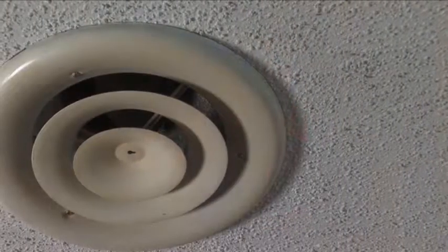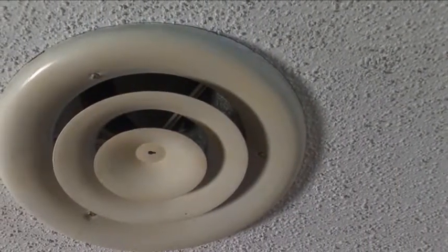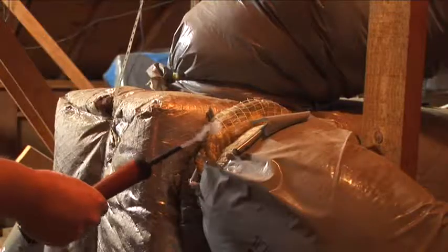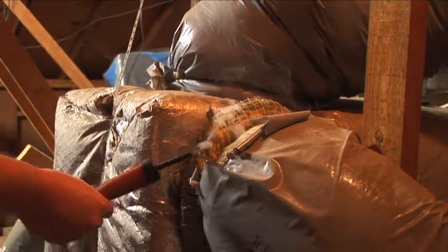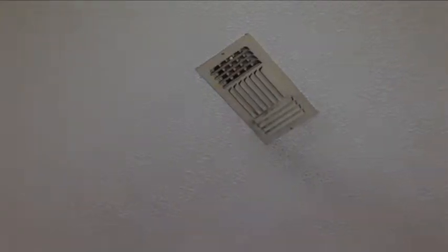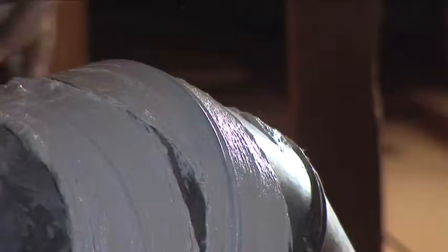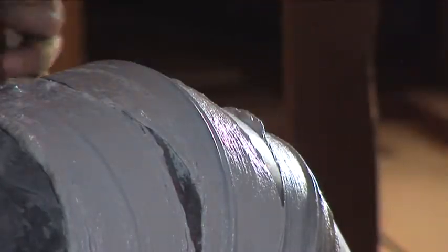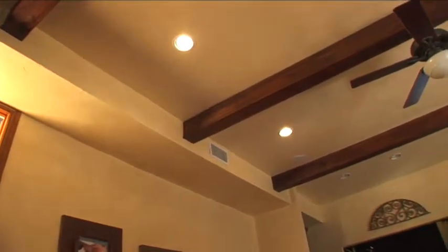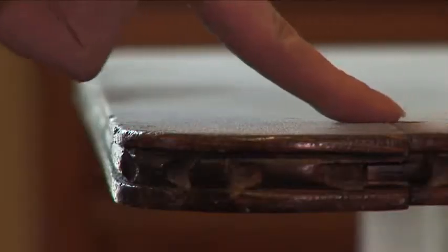Finally, some duct systems can be dirty and would benefit from being cleaned, but many authorities caution that duct cleaning is often a low priority. In fact, there's a very high likelihood that what you have is a leaky duct system that's pulled all that dirt into the system and into the house and delivered it to those registers. So I'm real big on getting your ducts sealed so that you make sure you don't suck that stuff into the system. You'll certainly see less dust in the house with a sealed system than one that is very leaky and outside air is entering on the return side and creating lots of dust and allergy problems.